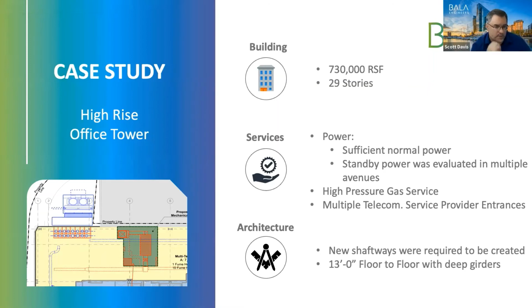And in the end, we ended up settling on establishing the maximum amount of airflow that we could get from exhaust. The picture you see here is a sketch we had done in Bluebeam. And in blue is actually the strobic type fan, similar to what Chuck showed for the last case study. And we essentially were able to fit on the smaller roof where we're locating the fan up to 80,000 CFM. So that now became our limit.